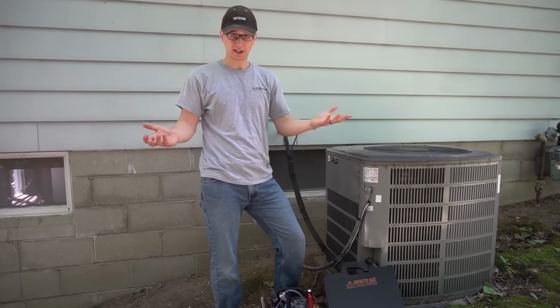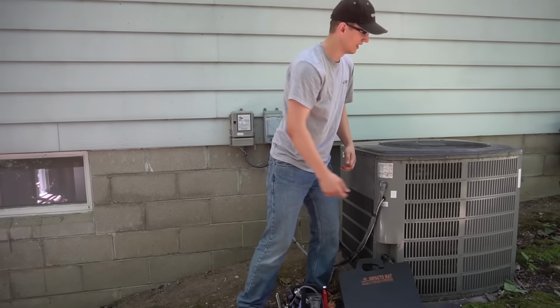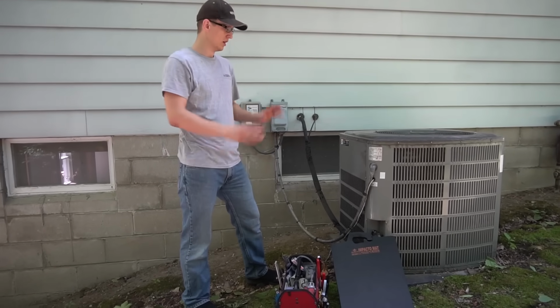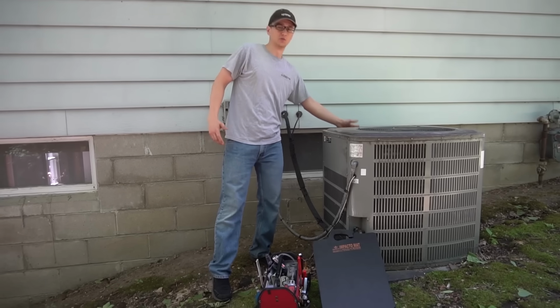And since this thing sucks stuff in through the sides, eventually it'll get plugged up, especially if you have a lot of stuff flying around like cottonwood seeds. This thing will be plastered, and that's actually very easy to clean. You can just use a hose to spray that right off. I made a video about that. I'll put that in the description below if you want. You can check that out too. You should clean your coil every now and again, maybe once a year or maybe once every 2 years. And generally the side towards the wall will be the dirtiest.